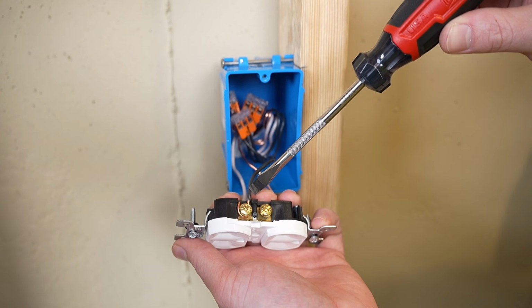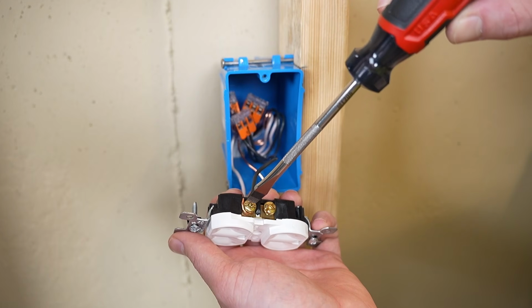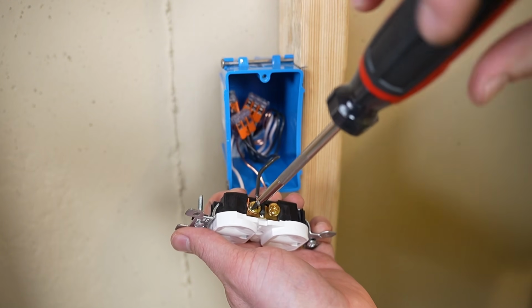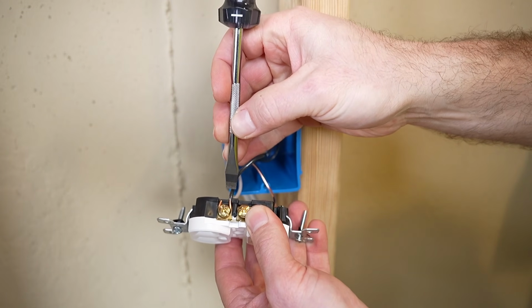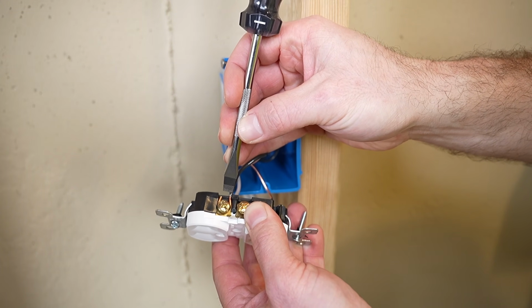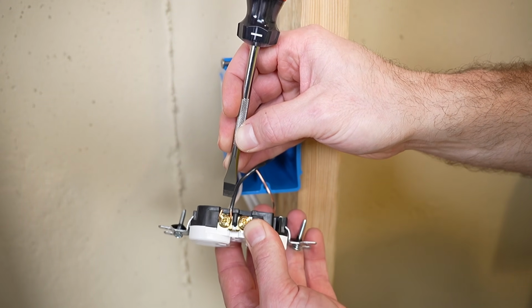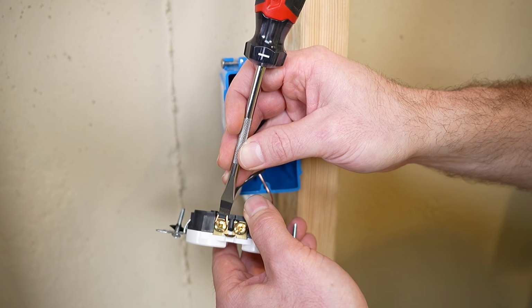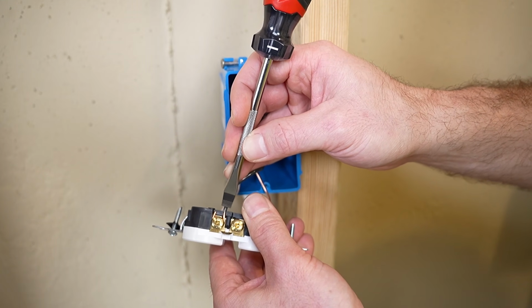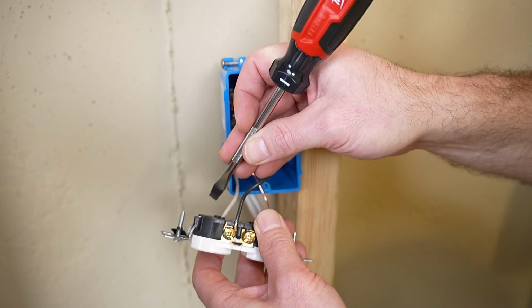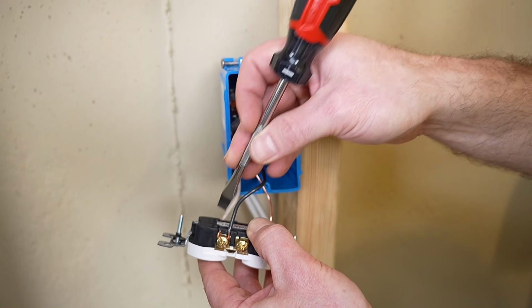Again, making sure that that wire is looping around the terminal the same direction the screw tightens. Additionally, you want to make sure no copper is extending beyond the back of the receptacle here. We don't want this copper stripped back any farther. You do not want to see hot or neutral beyond the back side of the receptacle.